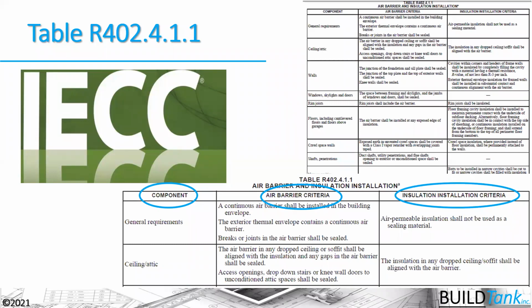So as I said before, like that tub on the exterior wall, it's telling us in this table that we need to add that supplemental air barrier because the drywall system isn't going to have the continuity behind that tub there. So it's an important table to understand in order to create that tight house and create that thermal envelope that we can use in our Manual J calculation.